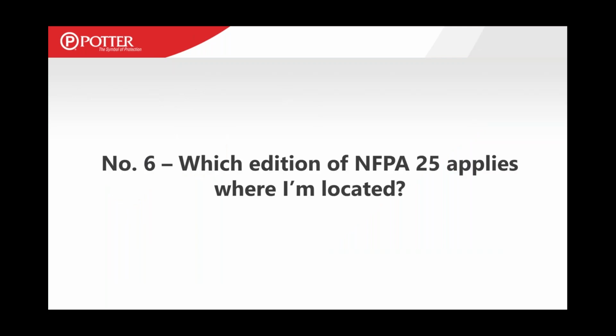Number 6, which edition of NFPA 25 applies where I'm located? This one also can be a little confusing sometimes. The thing to always remember is that NFPA 25 applies to really every system that's out there, every existing system. I always say there's a lot more existing systems out there than there are new ones.